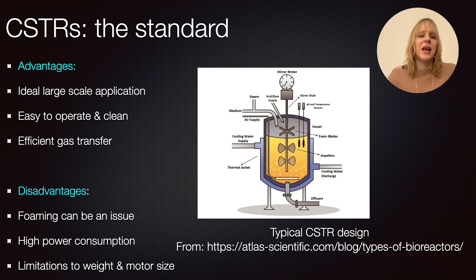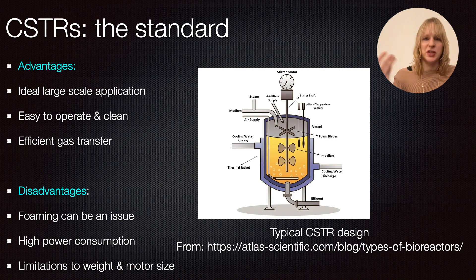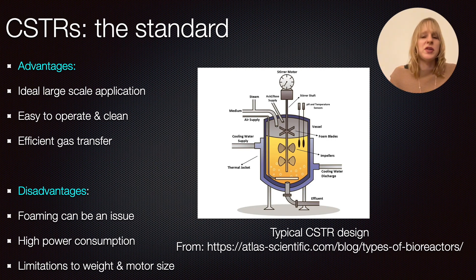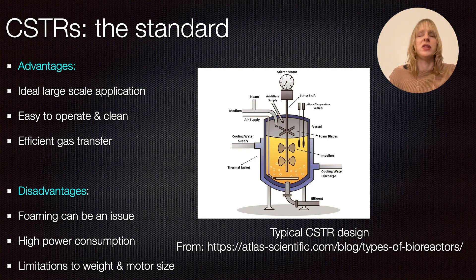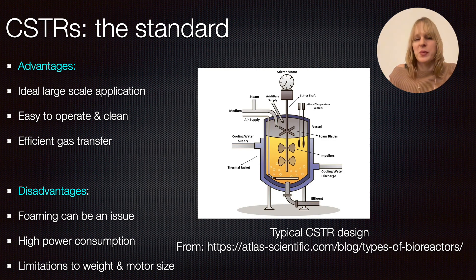Continuous operation can lead to high power consumption because you're continuously agitating the reactor, and there are some limitations in terms of weight and motor size. For very high volume applications such as wastewater treatment, there may be other reactors that are more suitable.